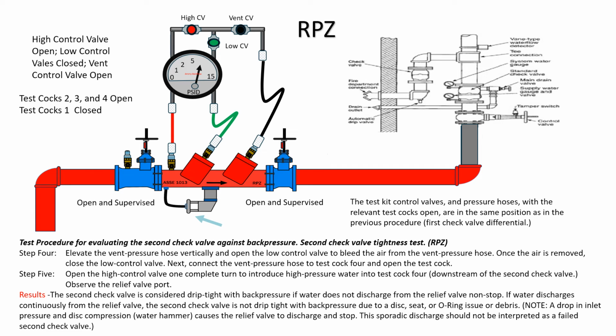Step 5. Open the high control valve 1 complete turn, to introduce high pressure water into test cock 4, downstream of the second check valve. Observe the relief valve port. Results. The second check valve is considered drip tight with back pressure, if water does not discharge from the relief valve non-stop. If water discharges continuously from the relief valve, the second check valve is not drip tight with back pressure, due to a disc, seat, or o-ring issue or debris. Note: a drop in inlet pressure and disc compression, water hammer, causes the relief valve to discharge and stop. This sporadic discharge should not be interpreted as a failed second check valve.